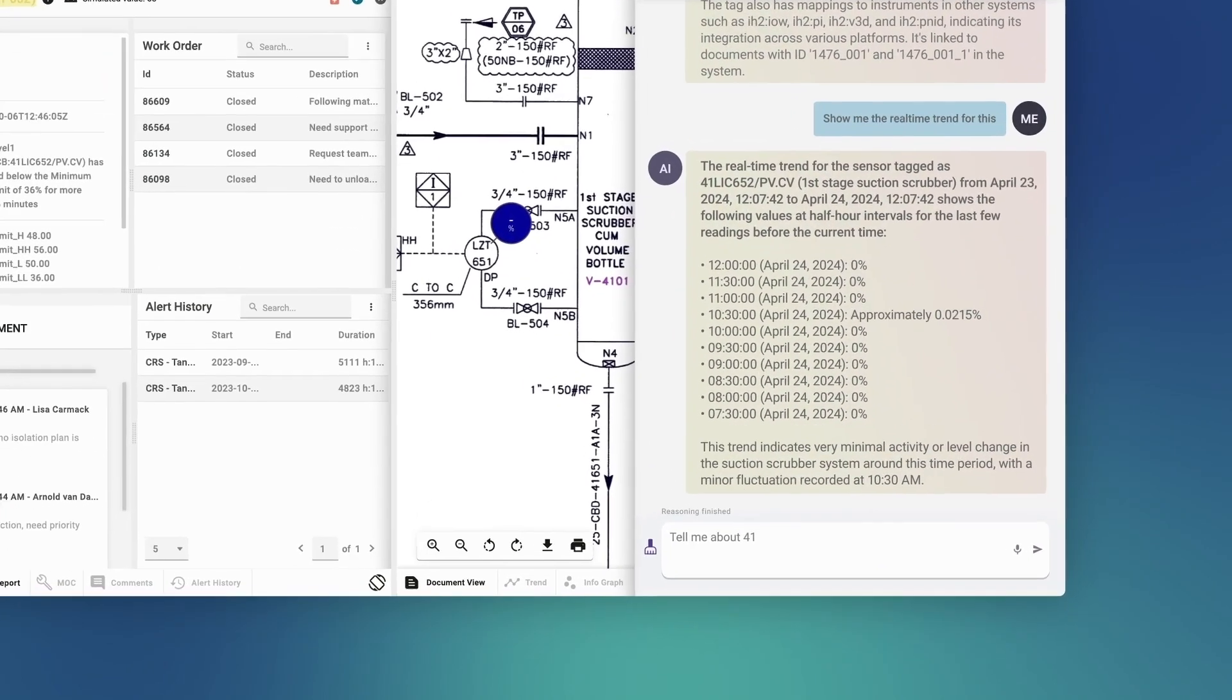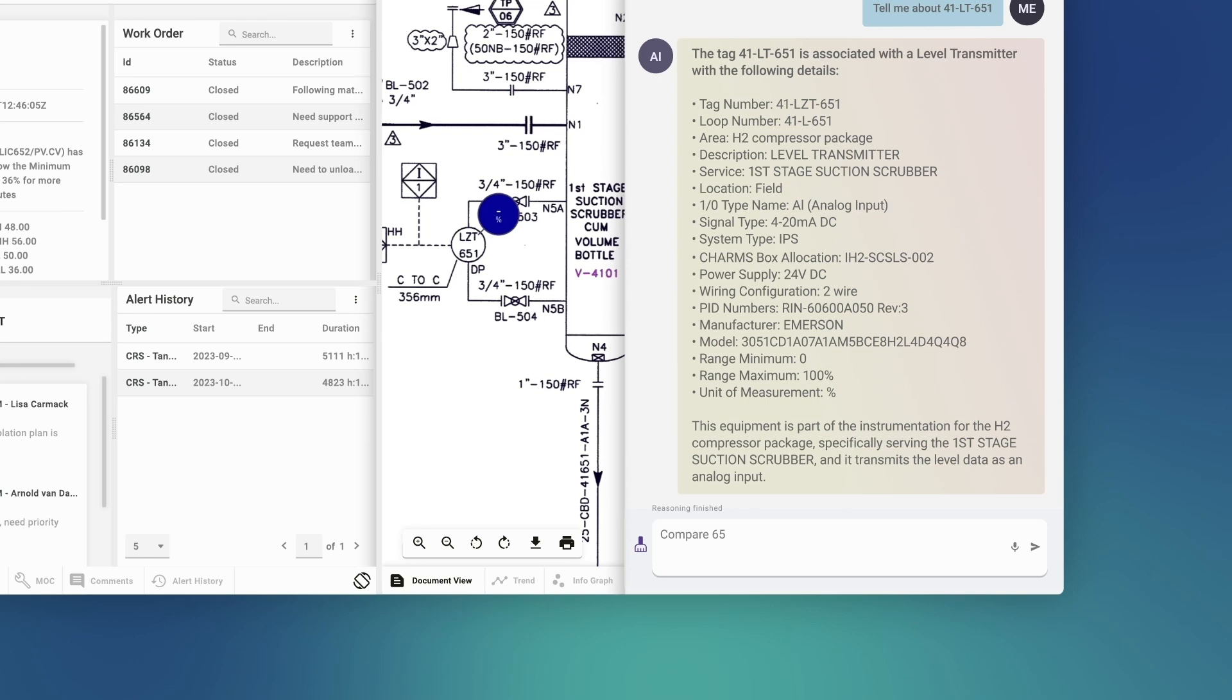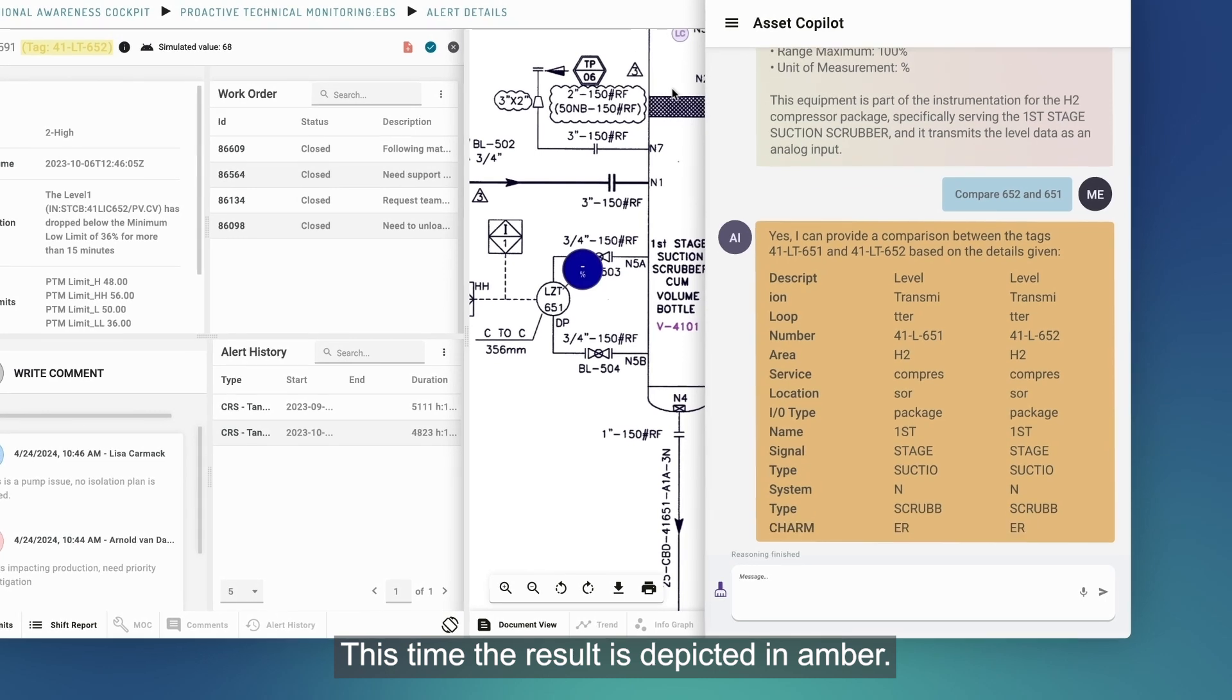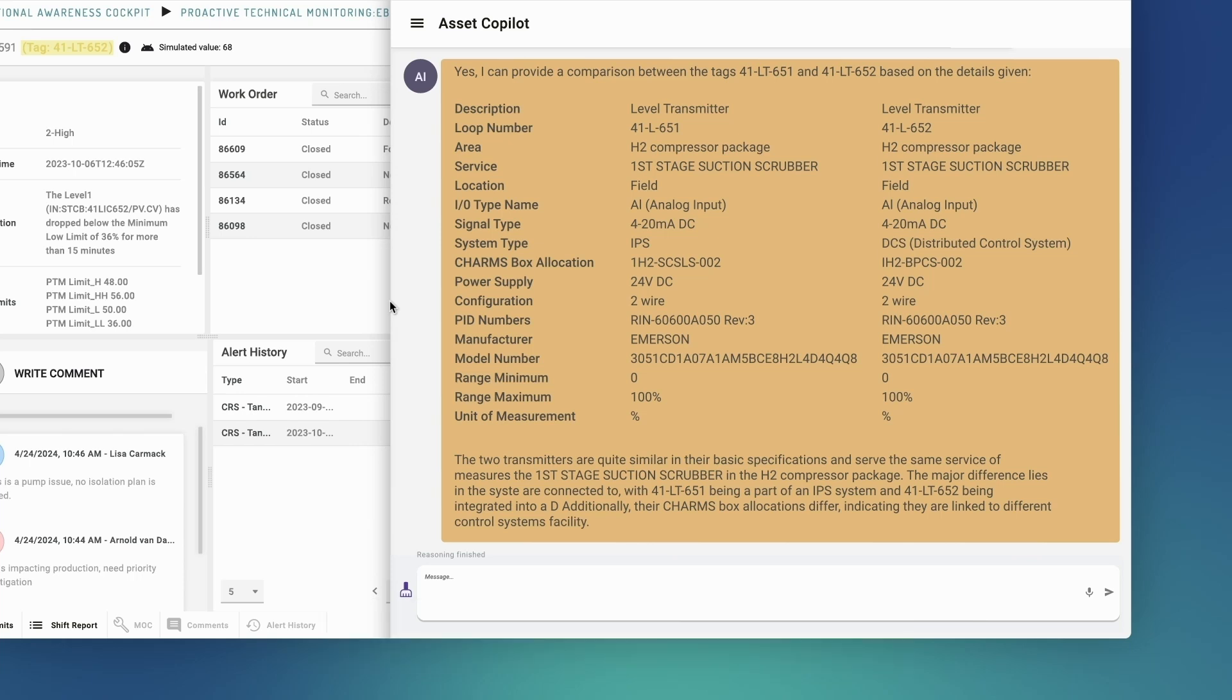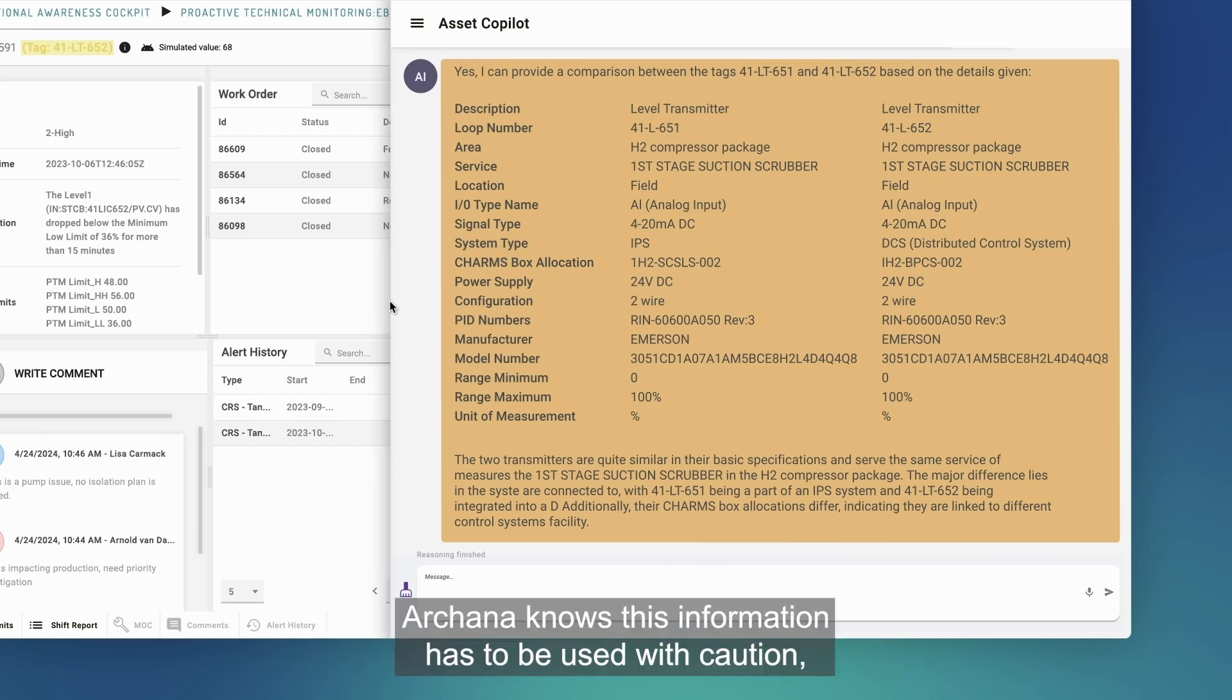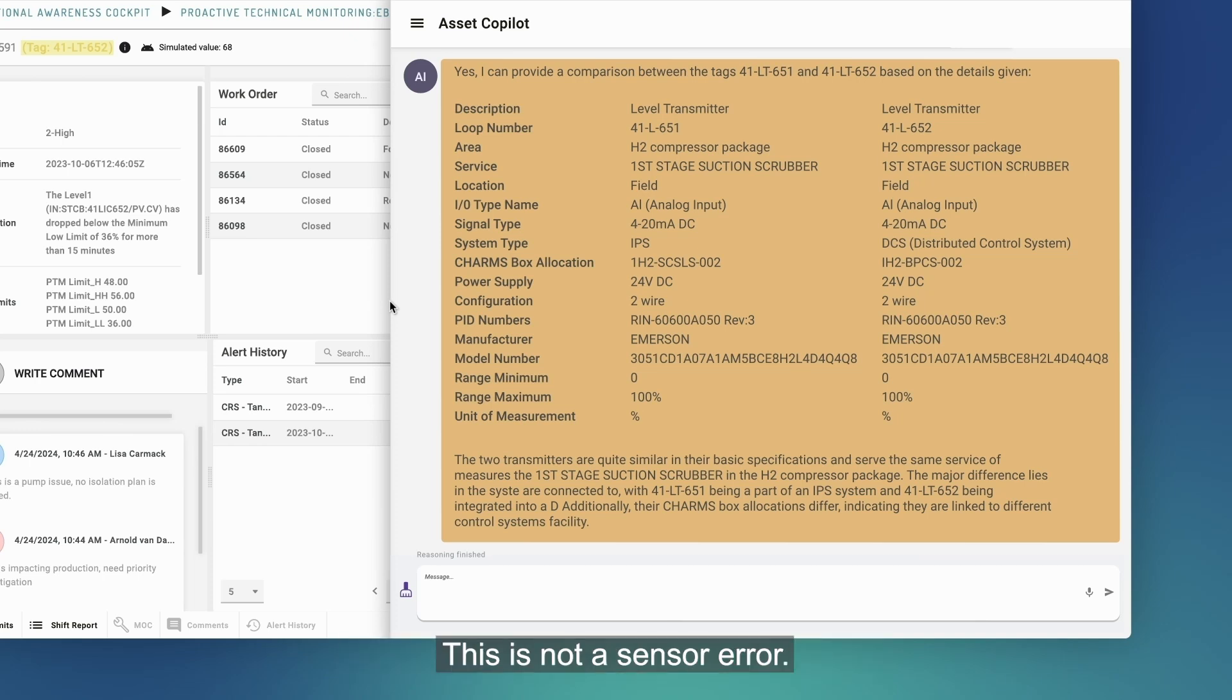Tell me about 41LT651. Compare 652 and 651. This time the result is depicted in amber. The comparison between the two sensors does not exist in the data. It is produced by the AI by combining, comparing, and summarizing. Archana knows this information has to be used with caution, but finds the comparison relevant nonetheless. Both sensors are reading similar trends. This is not a sensor error.